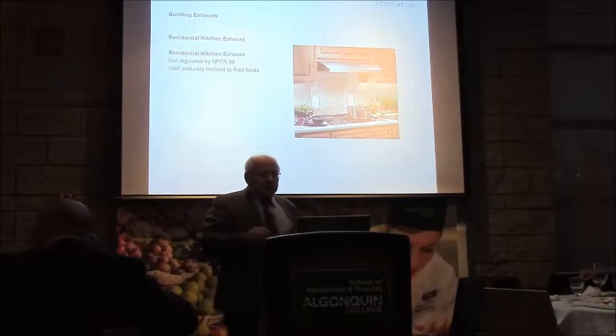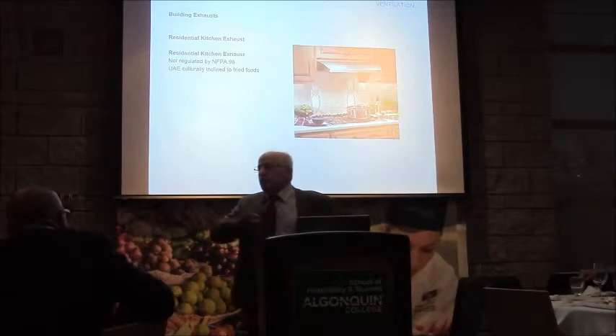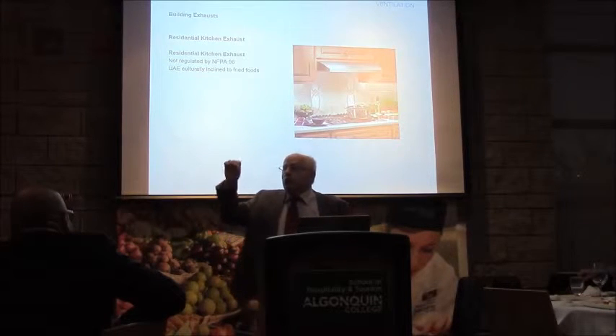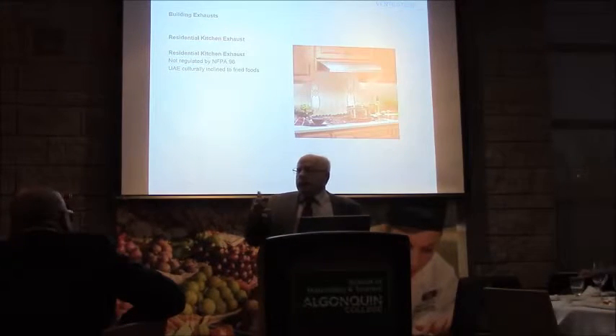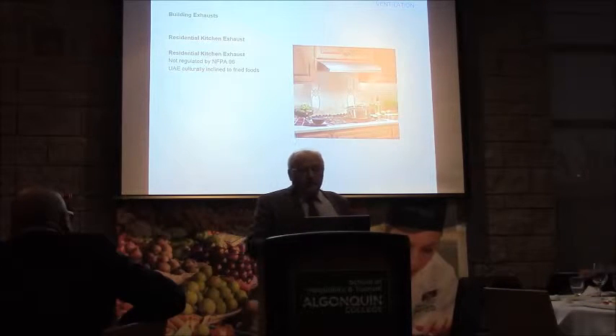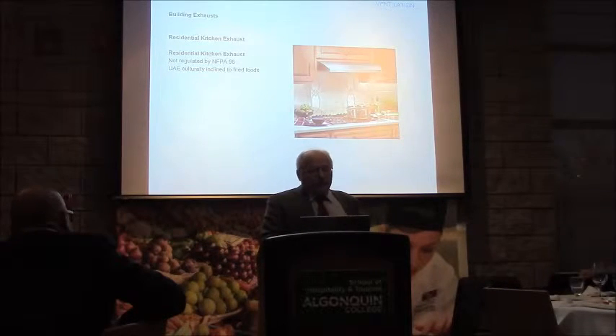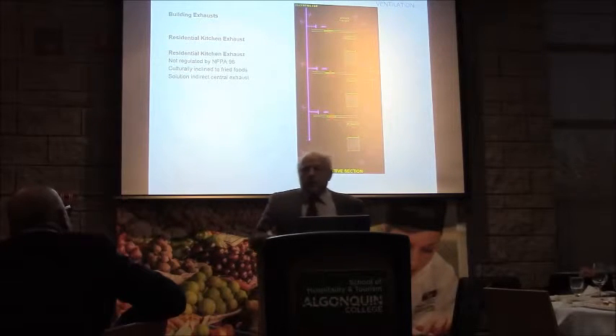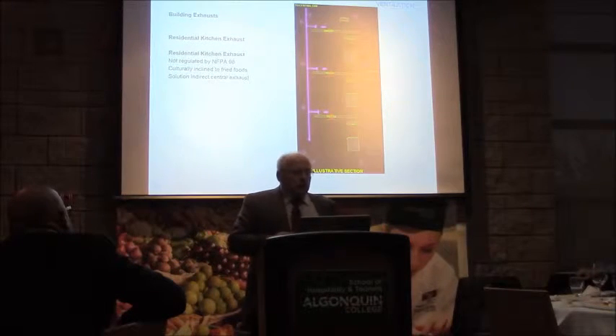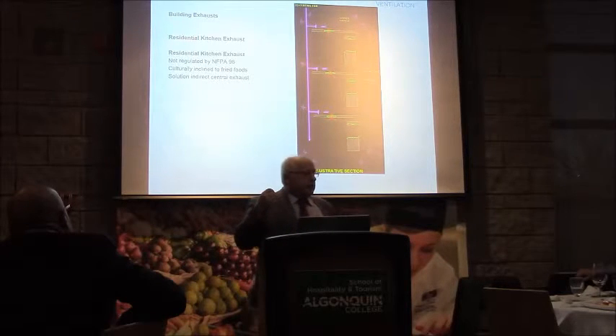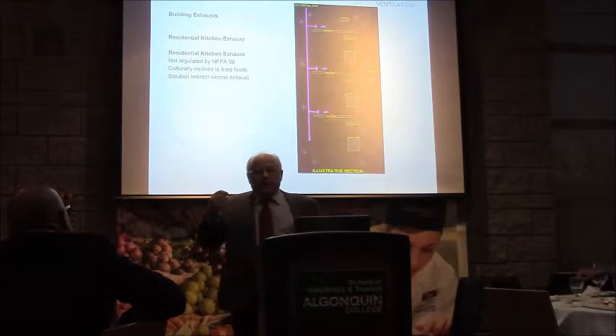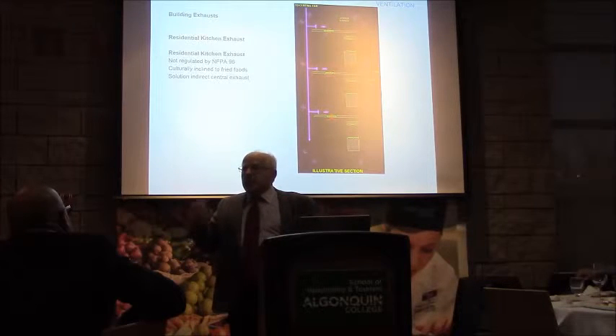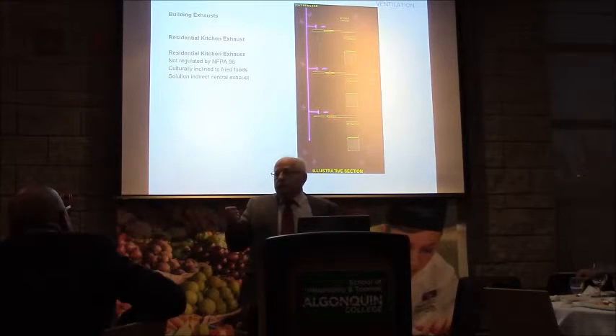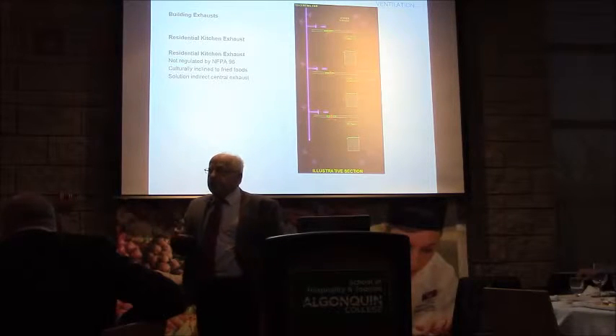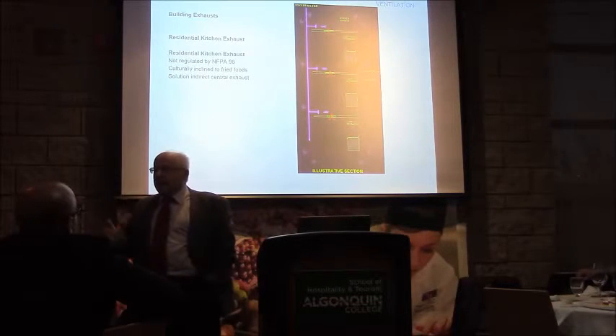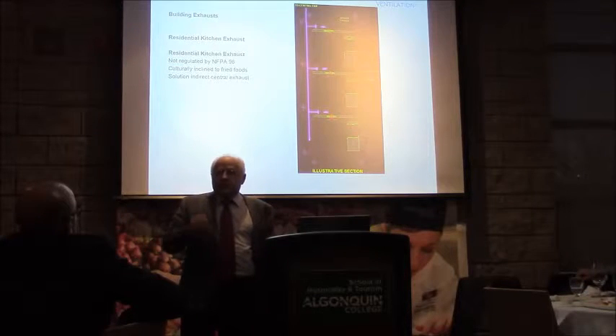In some other places, you don't have that option. If you have a full curtain wall, you'd have nowhere to go out the side of a building, and you have to do a collection system for something like kitchen smells. In a place like the UAE where fried foods is a big deal, you certainly wouldn't want to be collecting that kind of extraction in a duct system that's not made for it, because you're going to get grease impacting there at a certain point anyway, and that becomes a fire hazard, and it's just not a good thing.